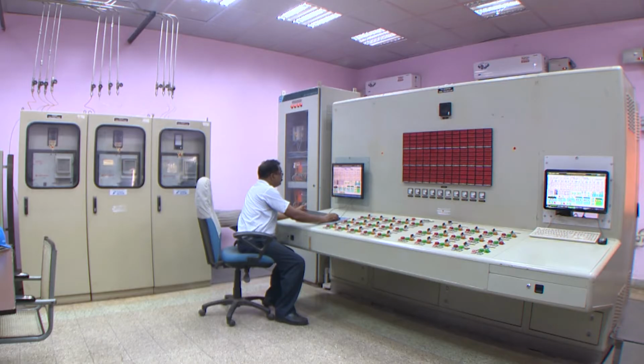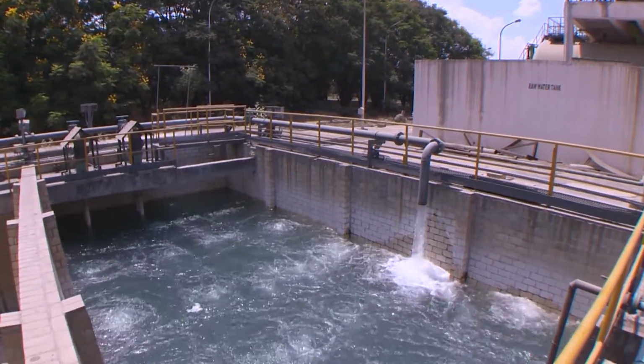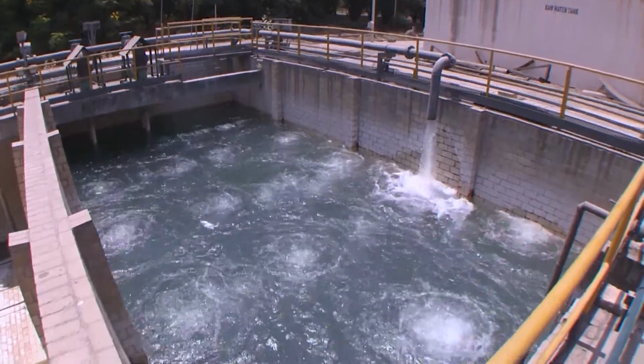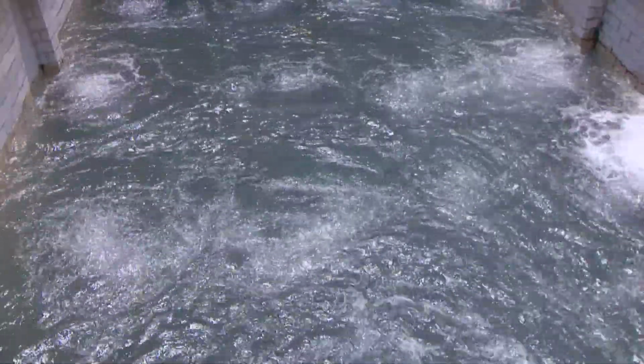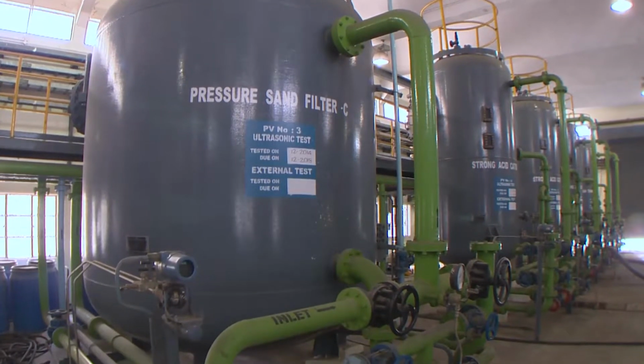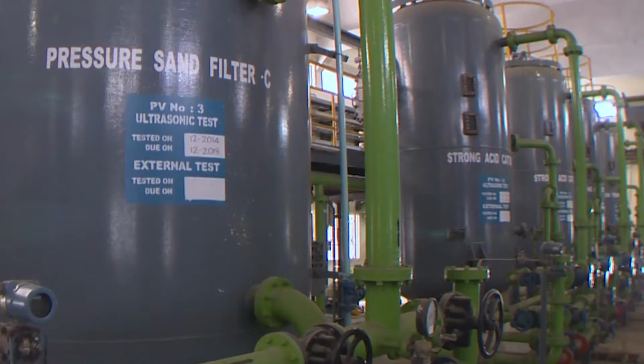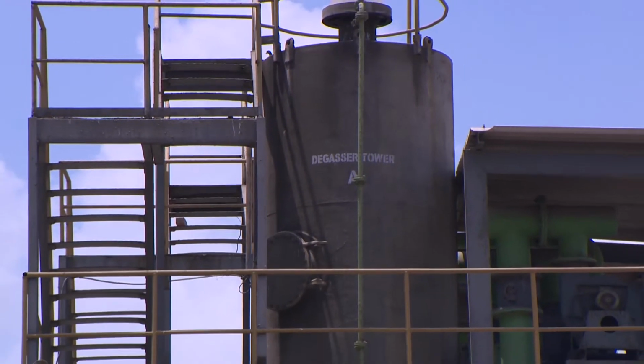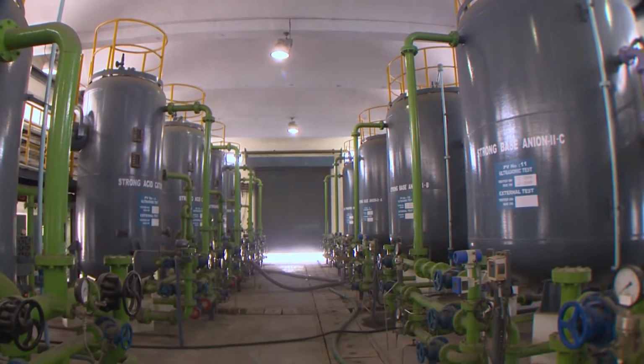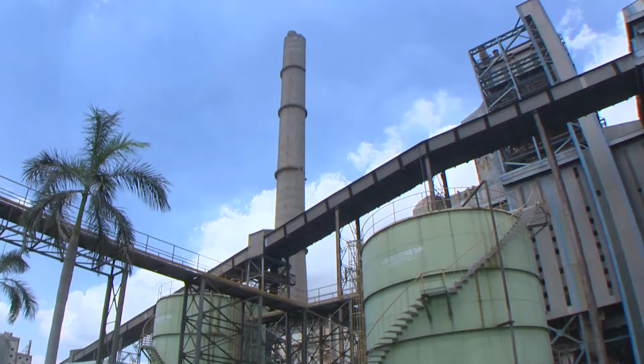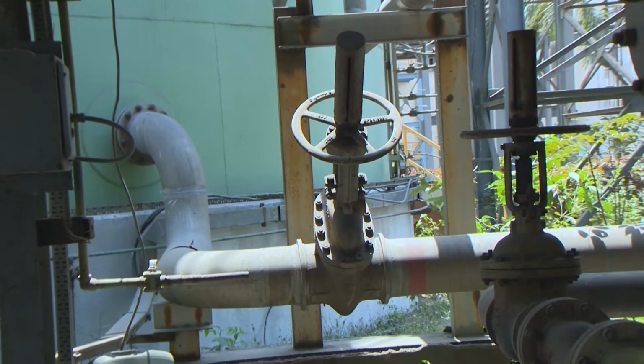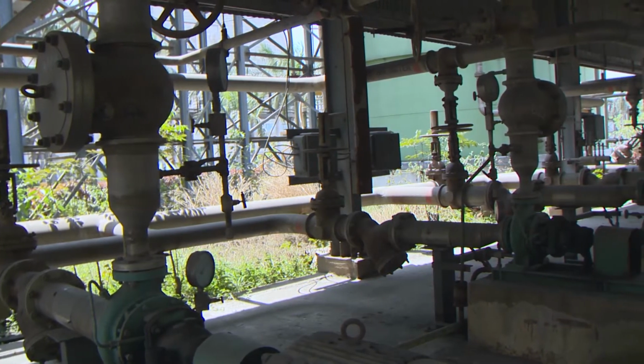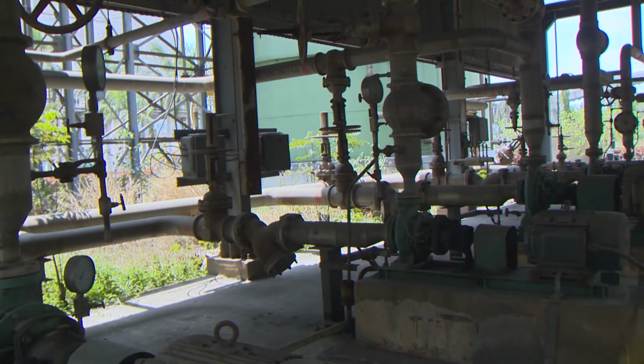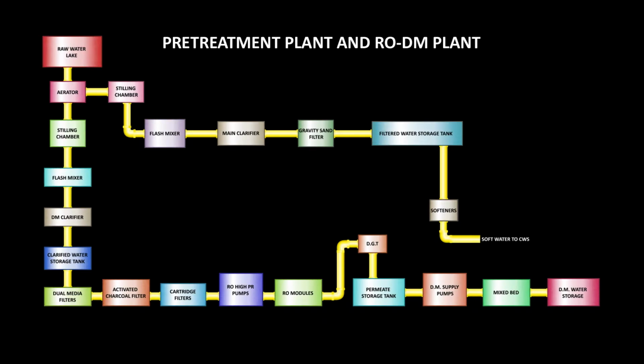Water chemical treatment plant supplies demineralized water for initial filling up of boilers and making up the water losses in thermal cycle. The borewell water passes through pressure sand filters, cation exchangers, degasser tower, anion exchangers for converting into demineralized water, and it is pumped into condensate storage tank from DM plant. Then the transfer pump supplies DM water to make up the system losses. Pre-treatment plant and RODM plant.